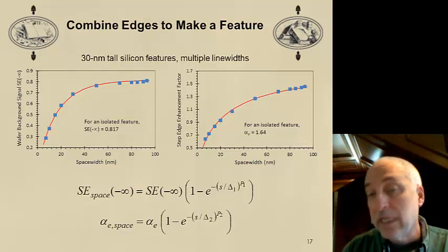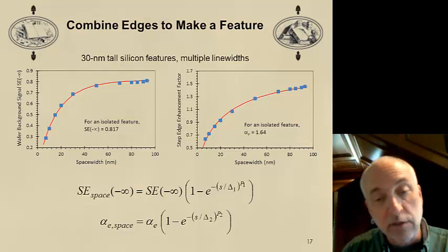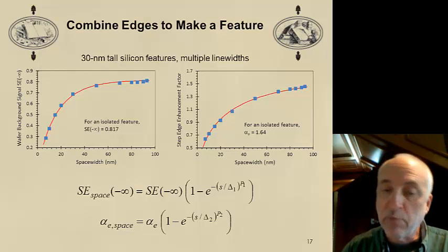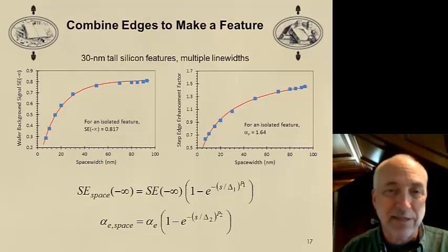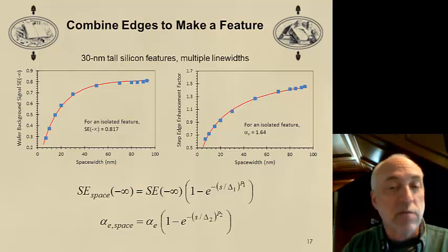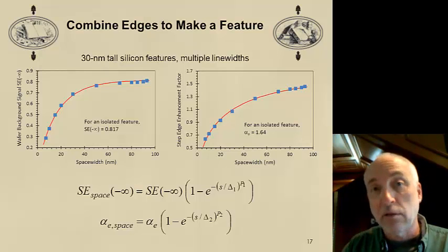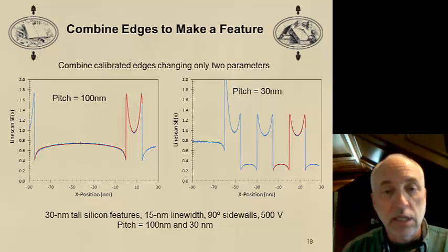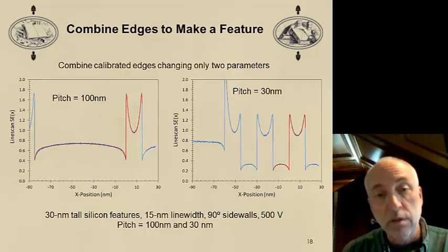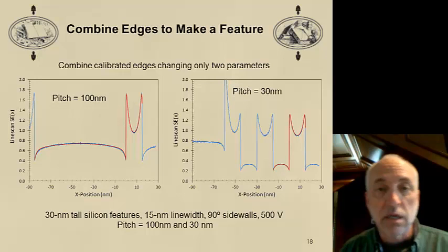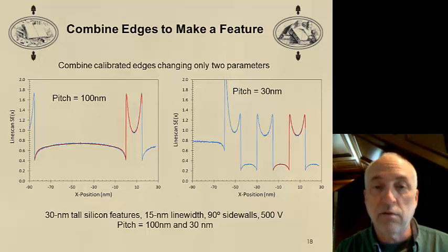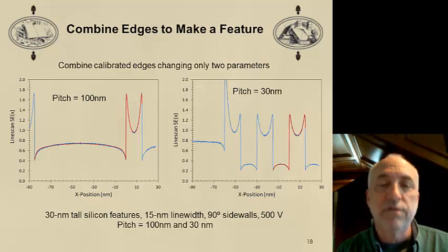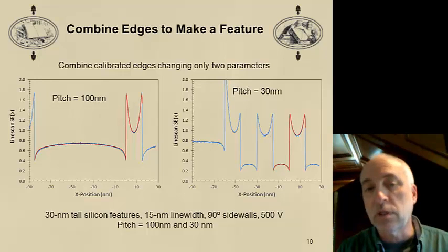The result now is a feature model that can take into account different step heights, and line widths, and pitches, and sidewall angles - many of the things that we expect to vary from feature to feature as we're measuring them in a scanning electron microscope. Now that we have a completed model that takes all these things into account, let's try it out. Here are the fits to the Monte Carlo results when we include this two-parameter change that is dependent upon the space width. You see that we get very good fits, and we tried this for a large number of feature sizes and pitches, and we got results close to this for almost all of the cases.